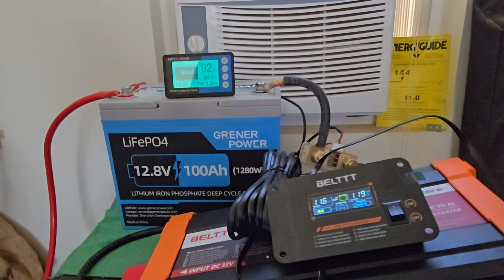This is a 12.8 volt, 100 amp hour battery, and the nominal voltage is 12.8 volts at 100 amp hours. The capacity at 20 amps is 300 minutes. Energy is 1,280 watt hours. The self-discharge is less than 3% per month. The cells are prismatic, and that's a good thing right there. Good prismatic cells.